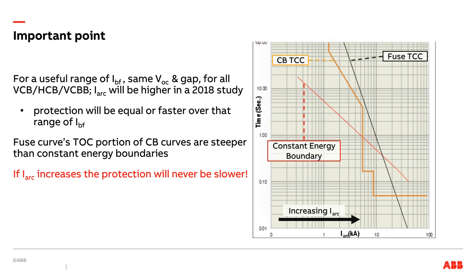On VCBB, you get more energy per unit time, but typically a much higher arcing current. So your protection is going to be operating further to the right on the curve. So even though it's a bigger explosion, it lasts so much less time that the net effect is less exposure. So you may be presented with the unlucky situation.